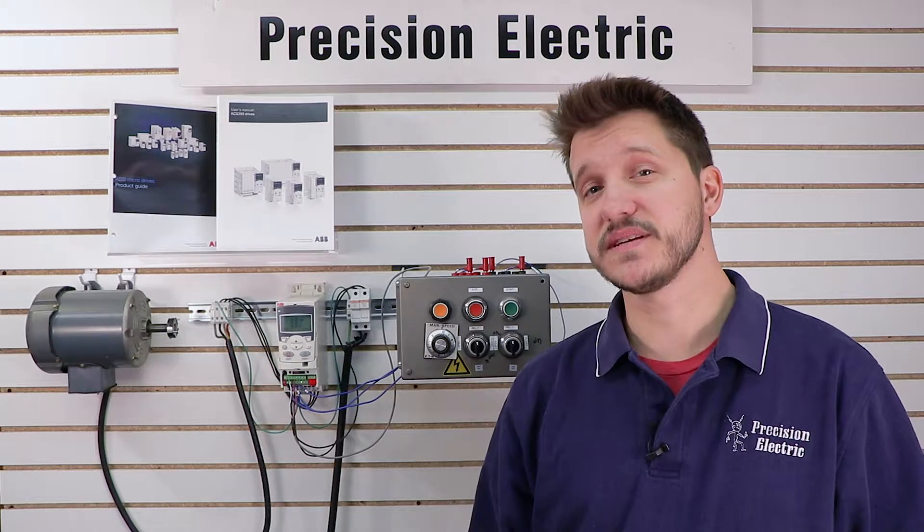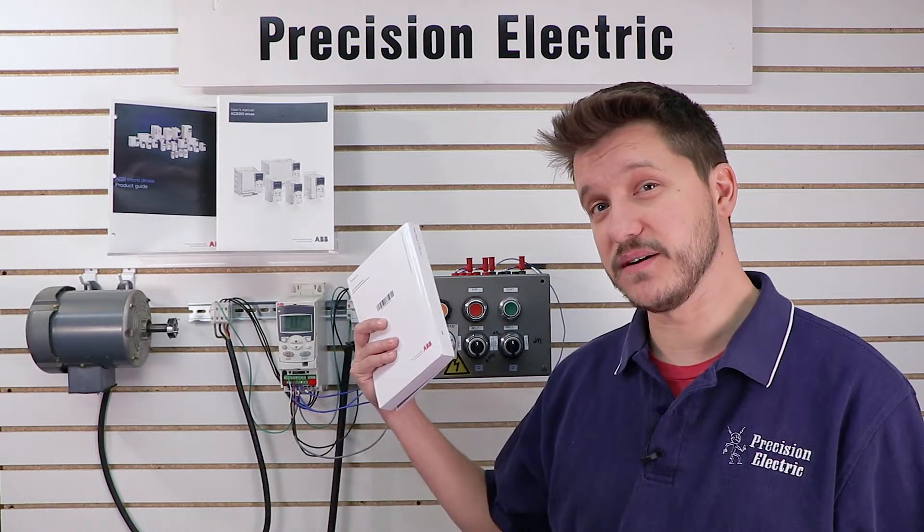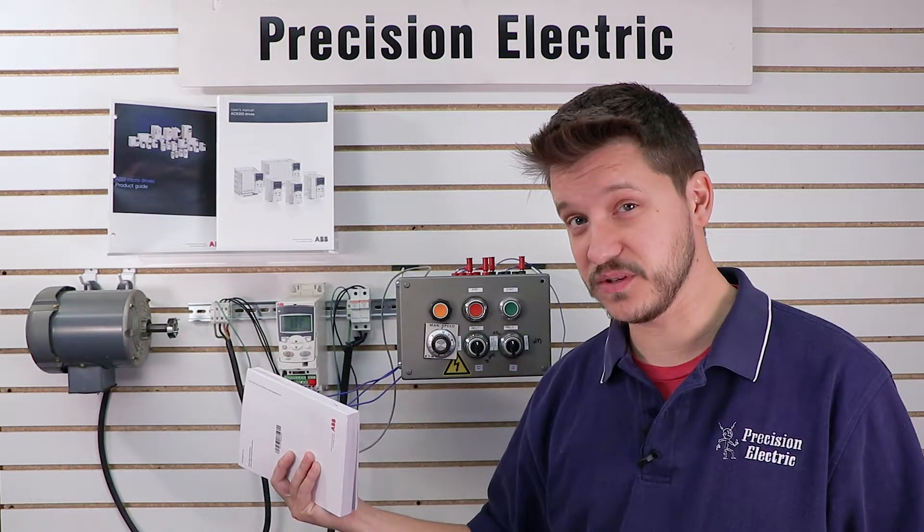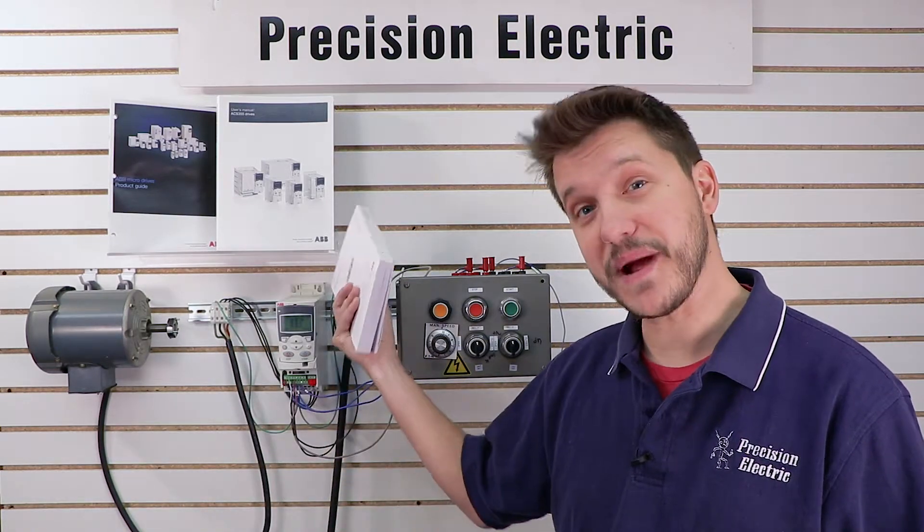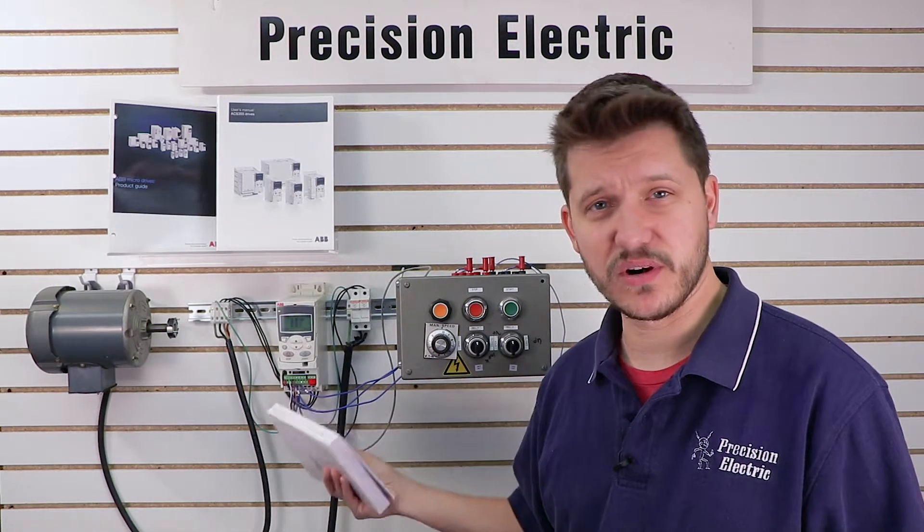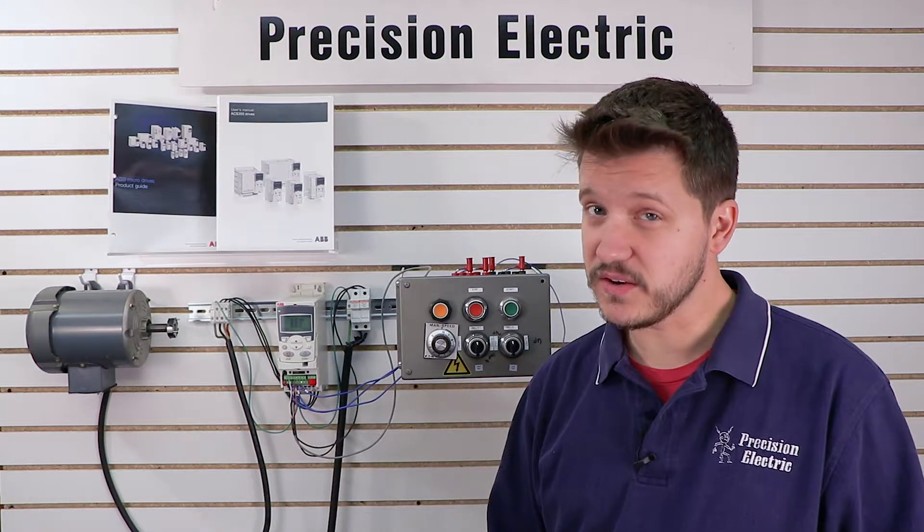Fusing protects the input of your drive. Whether there's an overload situation from the motor, maybe it's pulling way too much current, maybe had a dead short on the output, or a power surge of some kind, fusing is there to protect the input part of your drive. So we're going to go over how to size the fusing and wire the fusing.